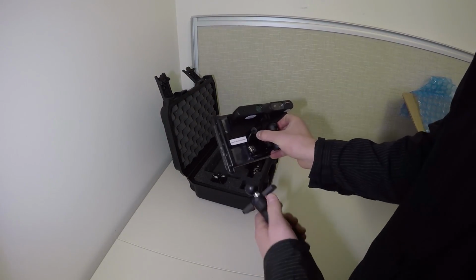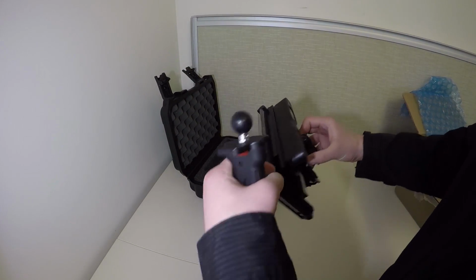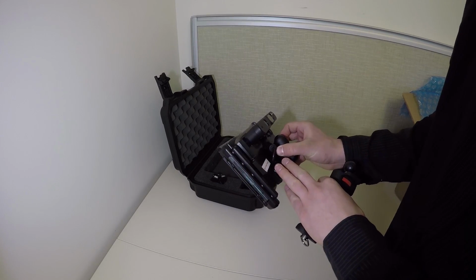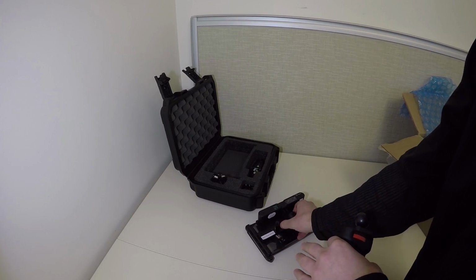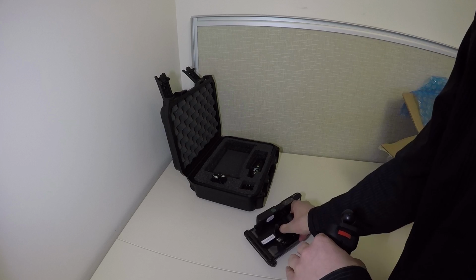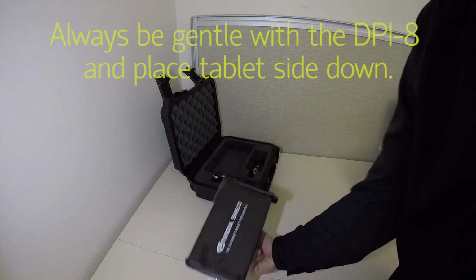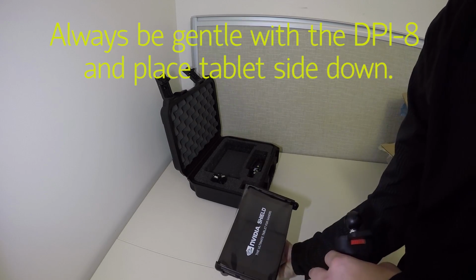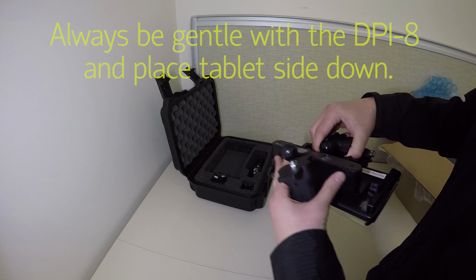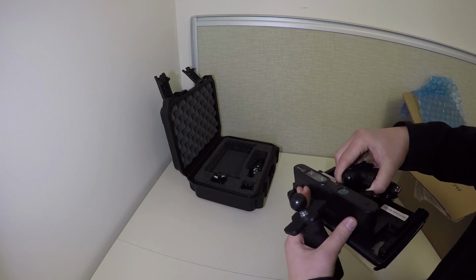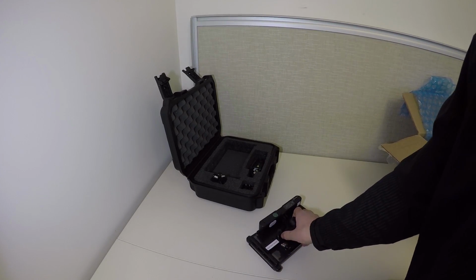So the first thing we're going to do here is attach the handle to the DPI-8. It's important to note that I'm always placing the tablet face down. You never, under any circumstances, want to set it the other way around. You have to protect this sensor at all times to preserve your calibration and functionality. Always set it face down.